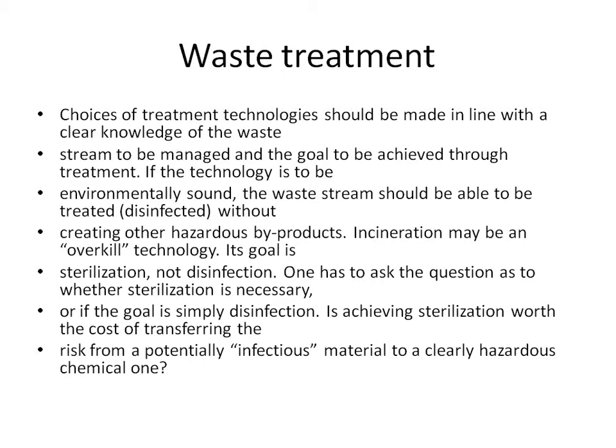So we sterilize them. There are things now called hydroclavers. A hydroclaver is slightly expensive, but it is a modern method. You break the waste into small particles, reducing it by maybe about 50% by quantity, then apply high pressure steam and sterilize it. Then you can put it into general waste.